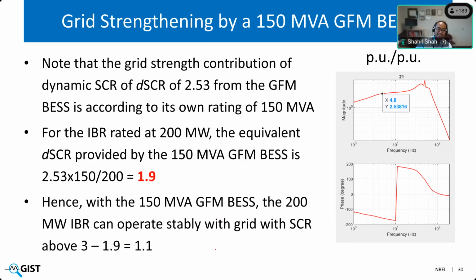So we selected a 150 MVA BESS model from a black box PSCAD model and did its Q by V frequency scan, as you can see here in per unit by per unit. Within the frequency range of 4 to 40 hertz, its gain is pretty much flat, but it falls towards the lower end at low frequency with a gain of around 2.53. So to be conservative, we selected this lower gain instead of selecting a higher gain somewhere around this point. So what it means is that this 150 MVA BESS is providing a dynamic short circuit ratio of around 2.5.